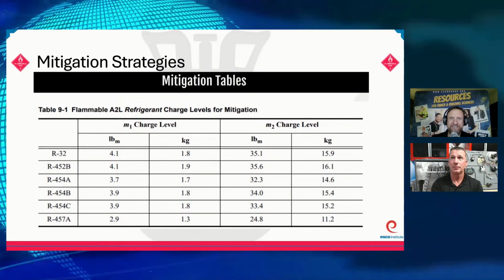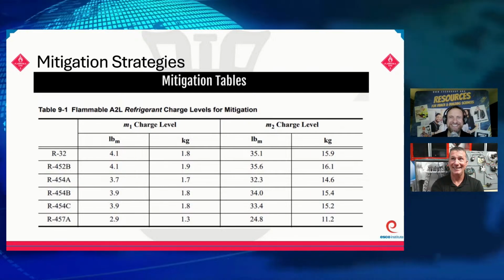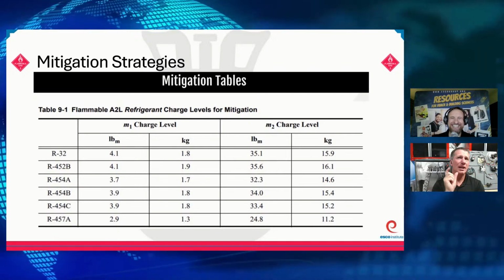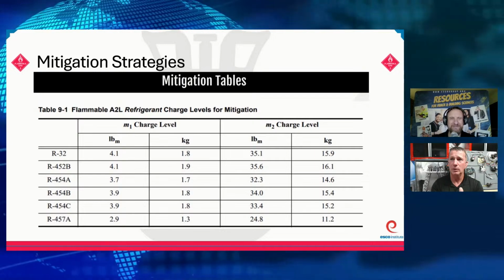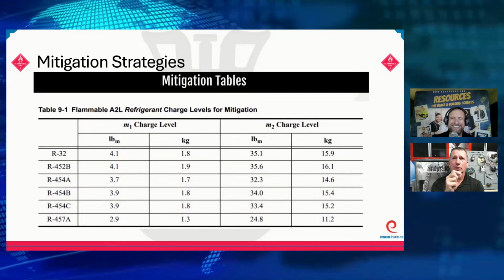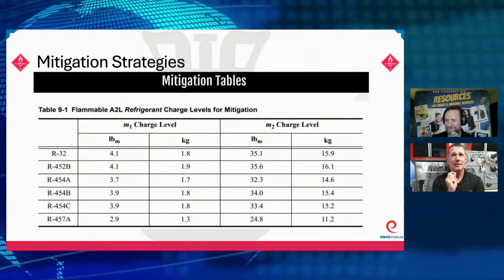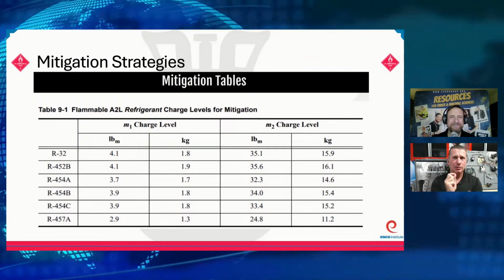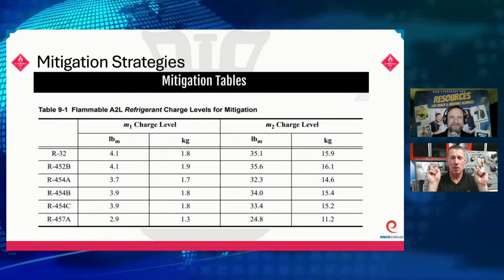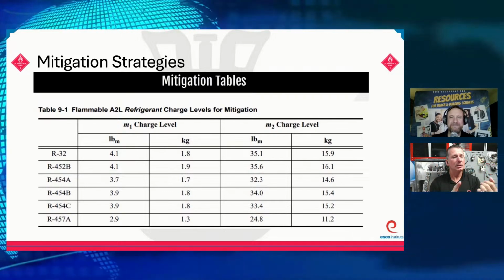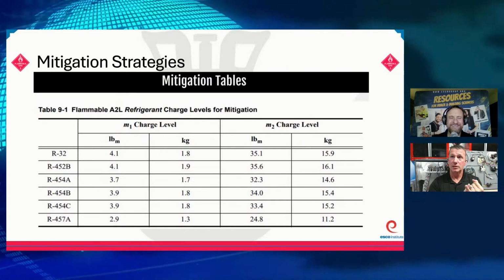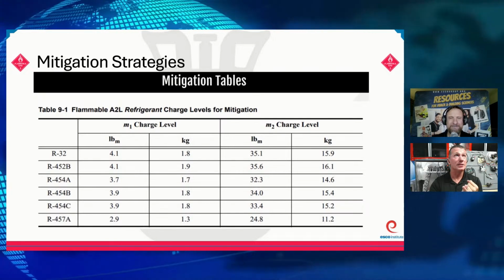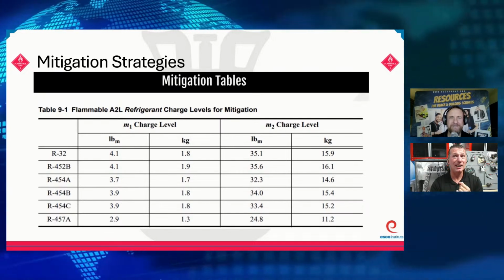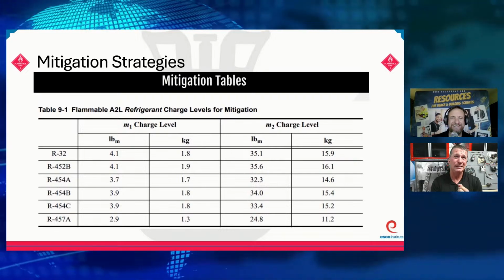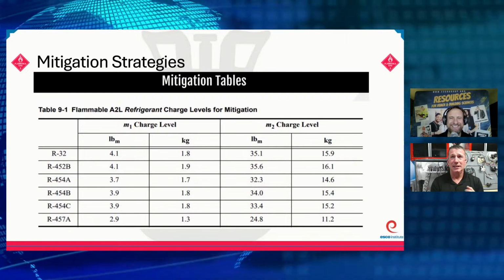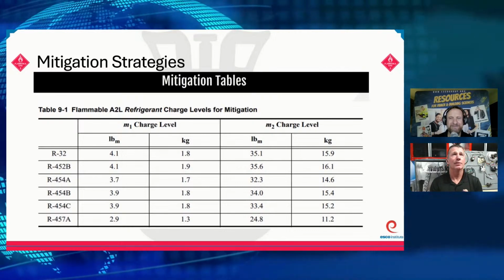Okay. And does it look any different than the R410A generation that would have been just previously before it? Oh, it has a sticker on it. A2L. Exactly. And it's going to have a little flammable sticker, which we'll talk about as well. But really, what we're looking at is the systems that will not be required to have mitigation will be in that approximately 4-pound range. So, ductless units, especially 1-to-1, probably not going to see any mitigation. Even if we get up into that 5-ton range, if it's a 1-to-1, there's a real good chance we're not going to see any mitigation because it's going to be under 4 pounds of refrigerant.